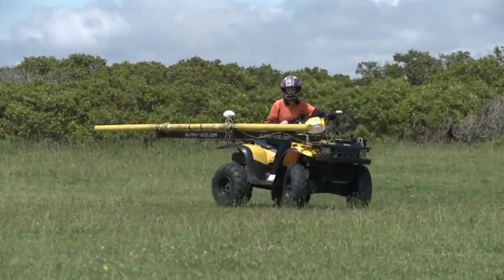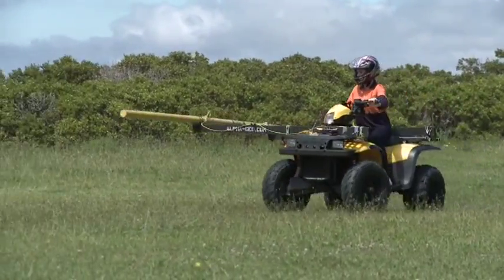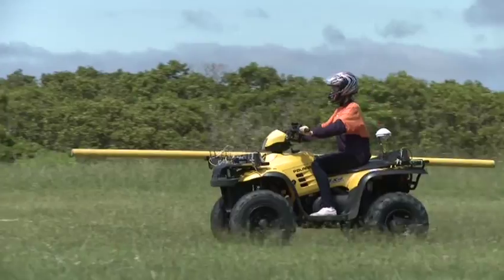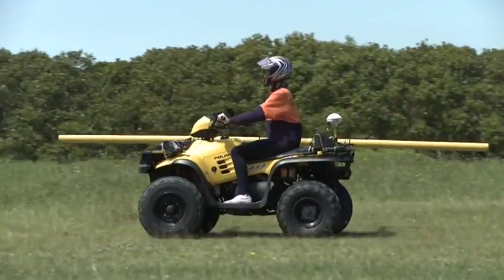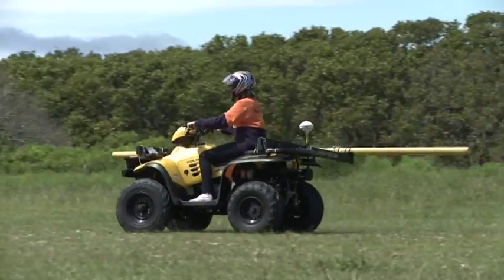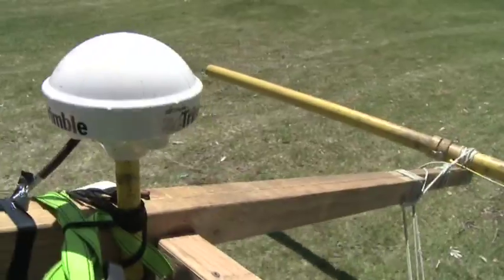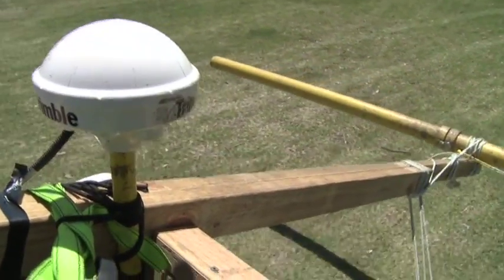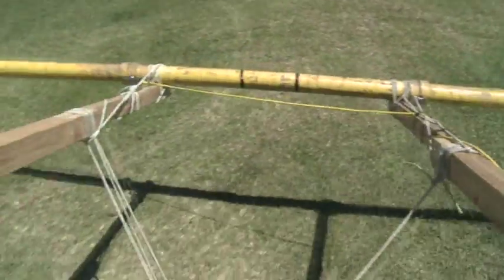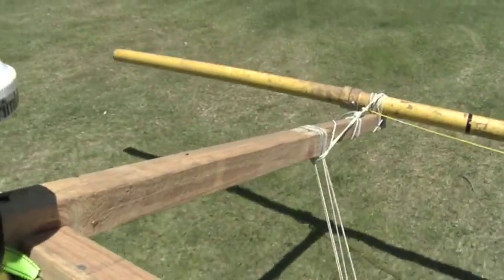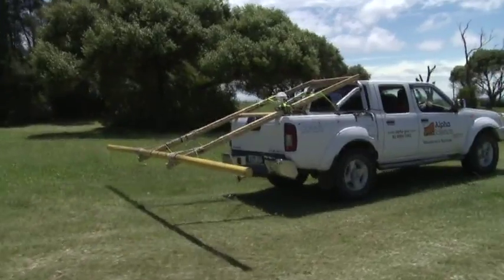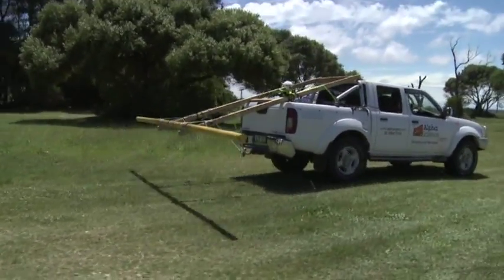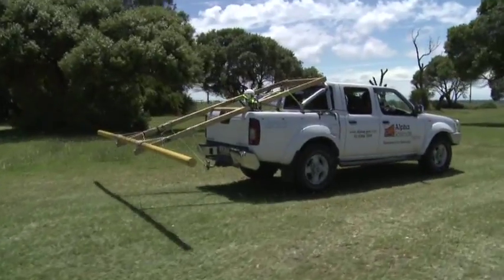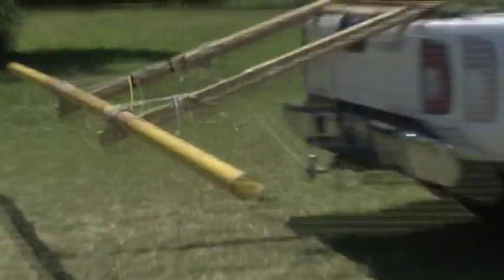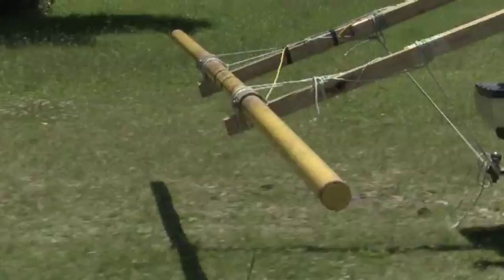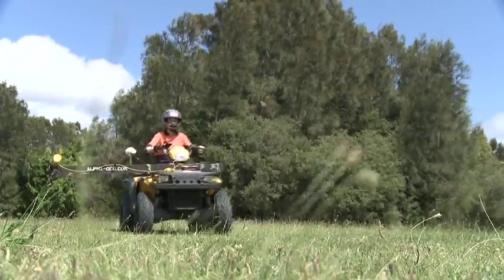Dualem is an electromagnetic instrument used for undertaking conductivity surveys for soil, groundwater, buried waste or metal, minerals, and bedrock mapping. The patented Dualem dual geometry array simultaneously measures conductivity and susceptibility to two distinct and easily quantified depths. Multiple measurements enable the estimation of the conductivity, susceptibility, and thickness in a layered earth.